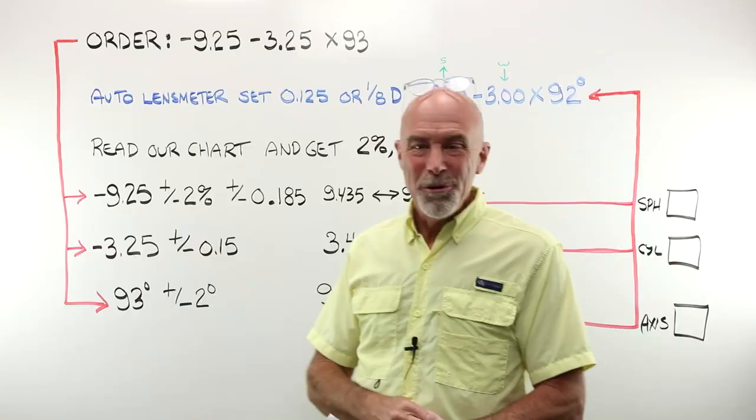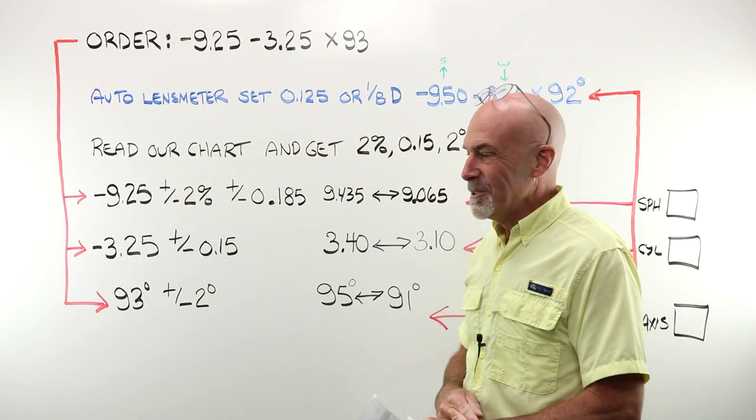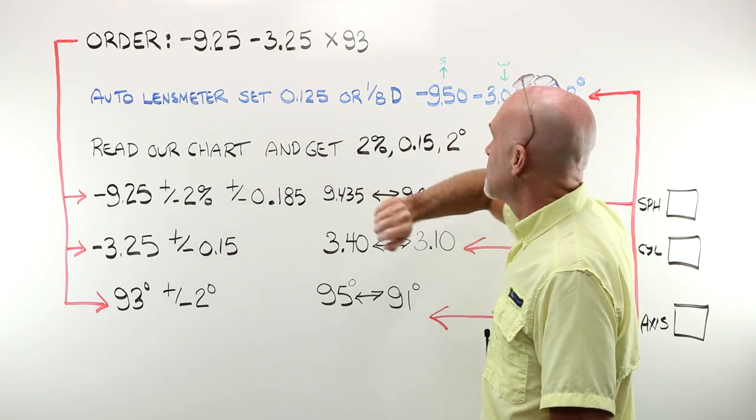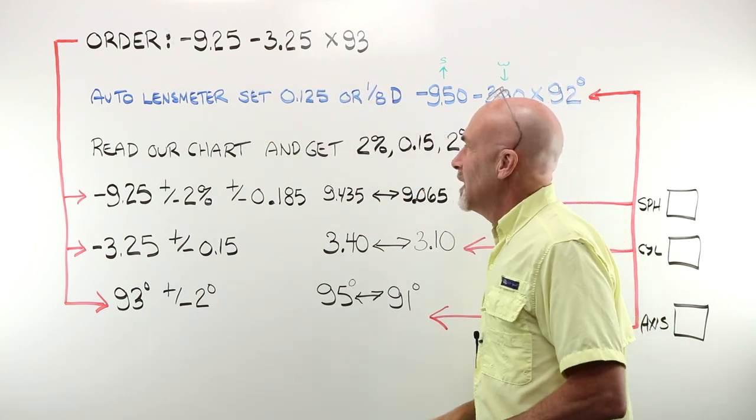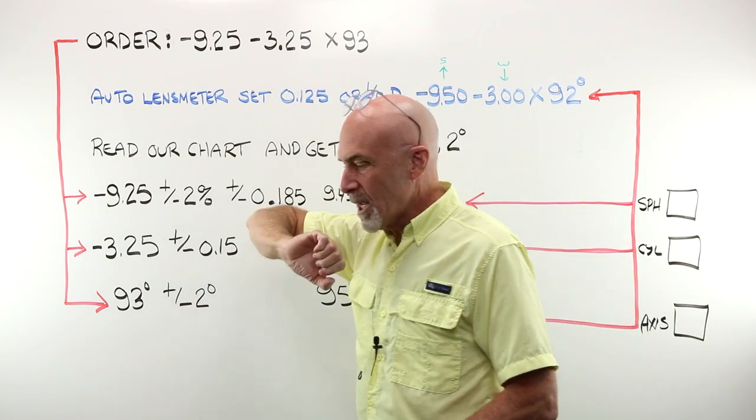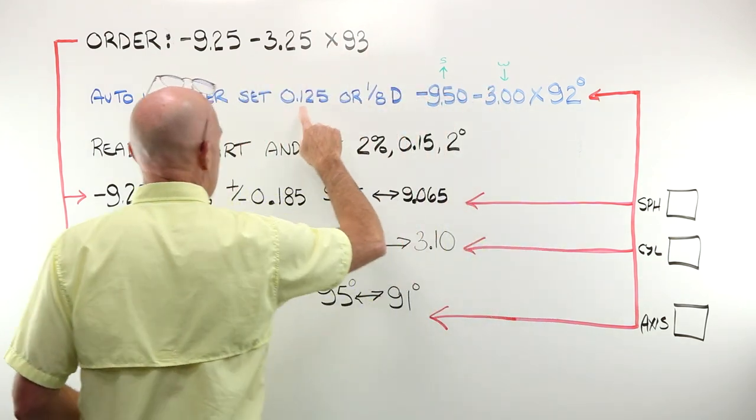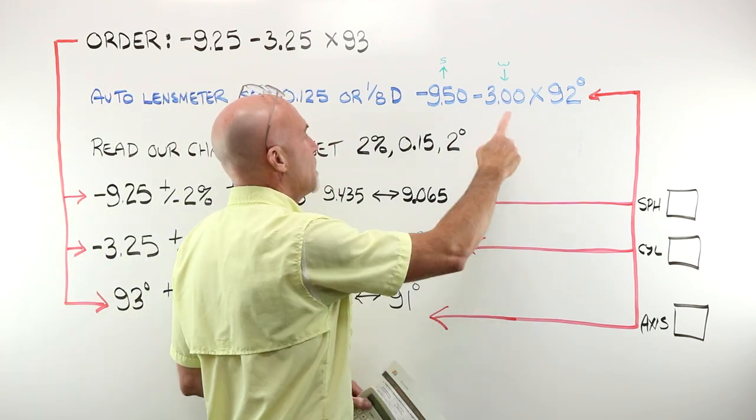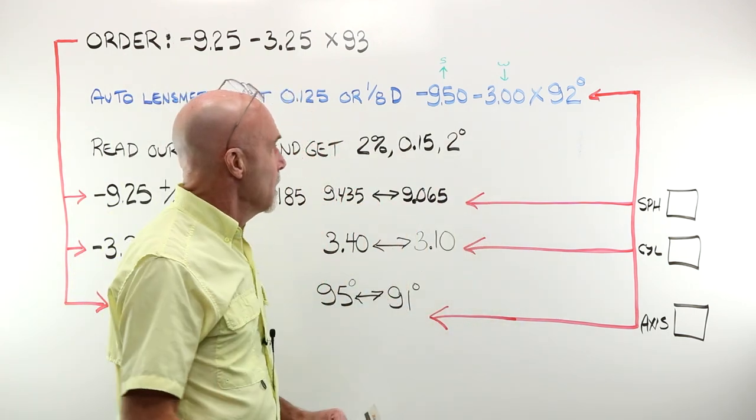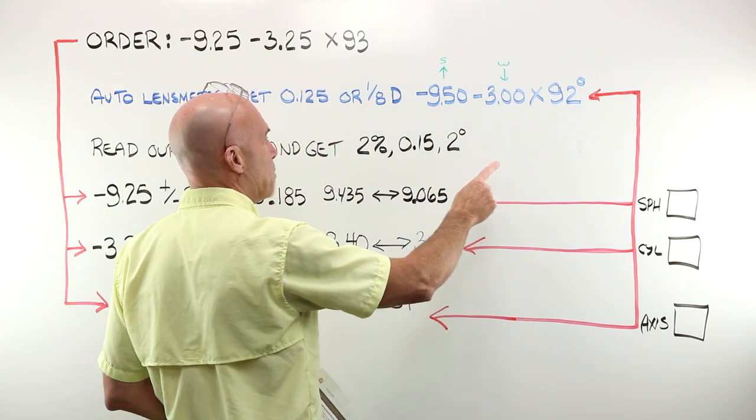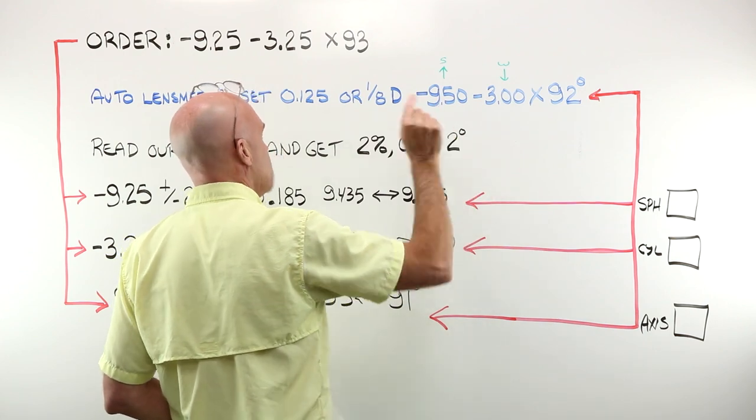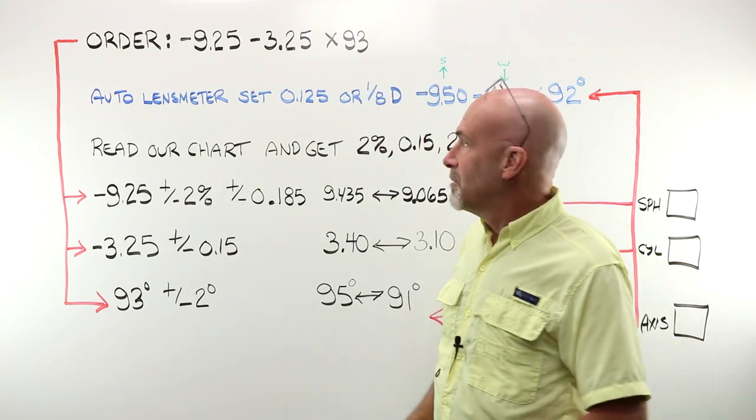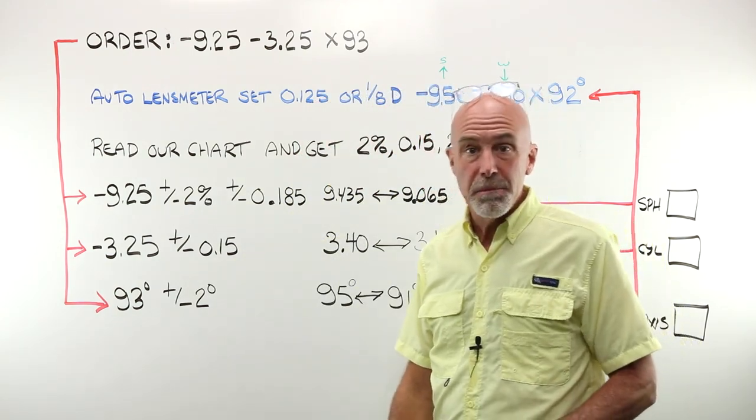Let's do one more. Are you ready for example number two? Good. Here we go. You ordered a minus 925, minus 325 at axis 93. You have got a gorgeous high-end auto lens meter set to read to the nearest .125 or eighth diopter step. You place the glasses in the auto lens meter. Line everything up correctly. Hit the print button and the ticket tells you you actually have a minus 950, minus three at 92. Are you going to be able to call up the customer and tell them to come and pick up their glasses or not?